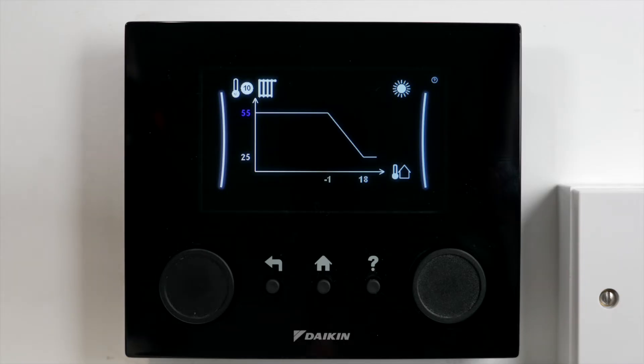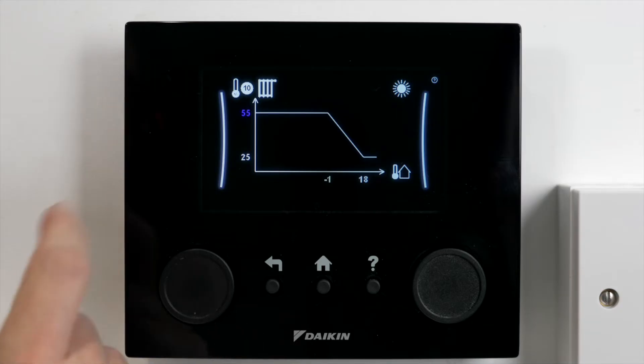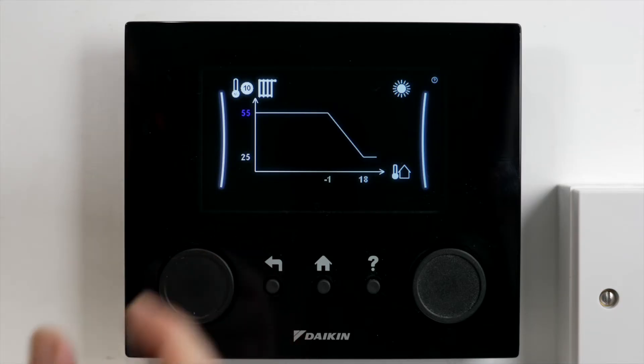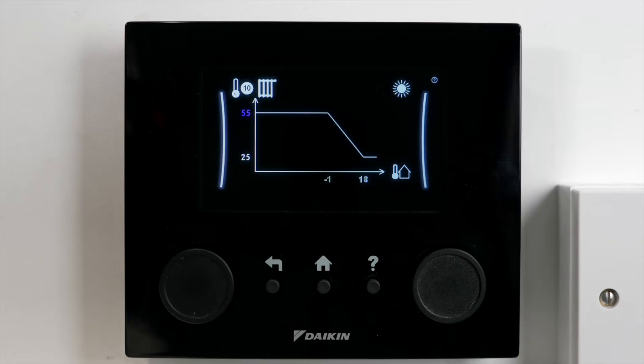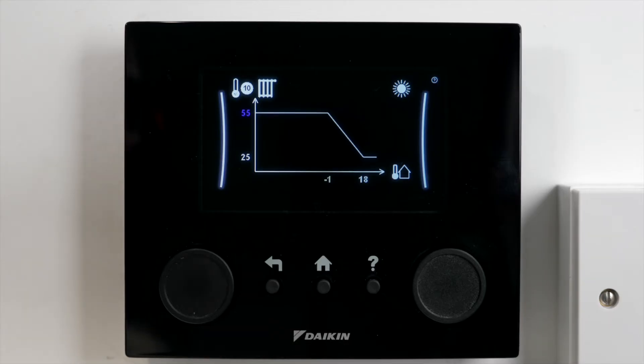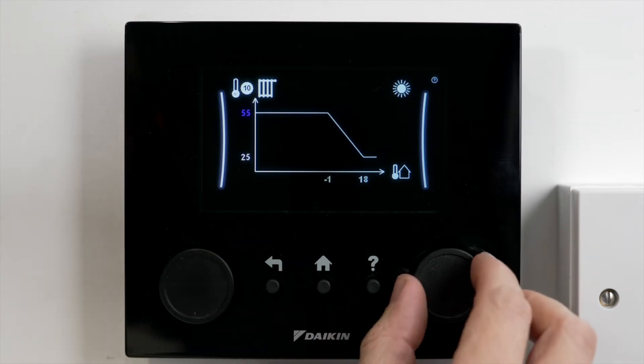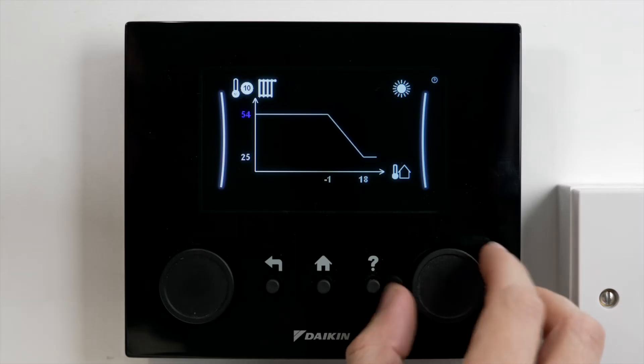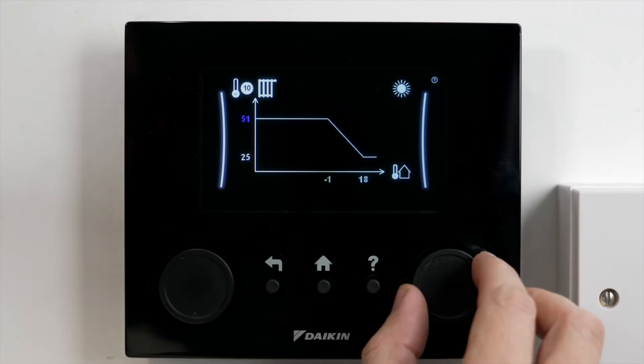But how do we set it up? On the side menu you'll get some numbers — these are our leaving water temperatures, which means our flow temperatures, or the temperature of the water as it leaves our heat pump. The first thing to do is look at your design documents and see what your system is designed to as a flow temperature. I'm going to go for a 50 degree flow temperature.